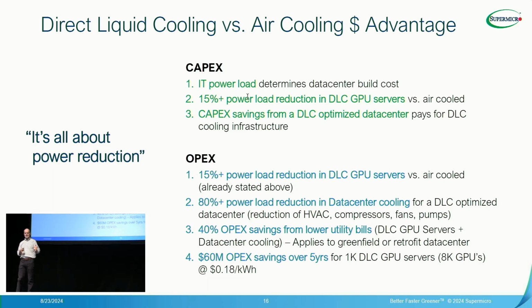Secondly, OpEx: what are the operating costs over time? In that data center, we talked about getting rid of the CRACs, getting rid of the air handlers, getting rid of those industrial fans. The actual electricity and water bill you're paying on a monthly basis between air cooling and liquid cooling, you could reduce by 80%.